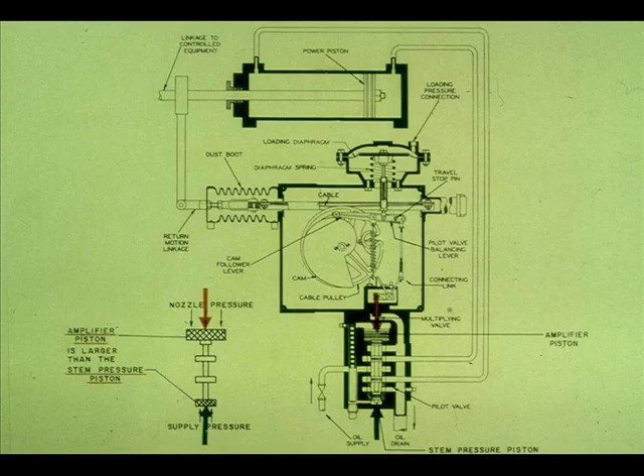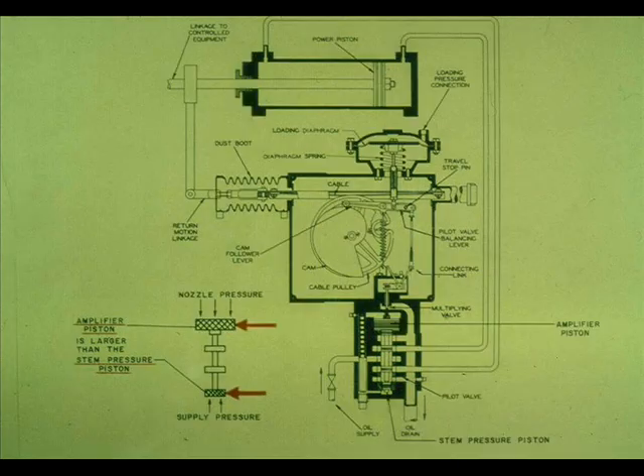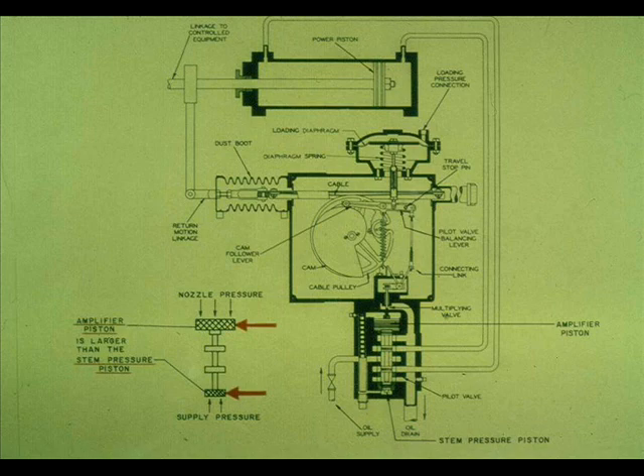Here you can see the two forces that act upon the pilot valve. The variable pressure is from the multiplying valve. The constant pressure is the supply pressure acting on the stem pressure piston. Notice that the amplifier piston area is larger than the stem pressure piston. This is why a small force on the amplifier piston can make the stem pressure piston lower.